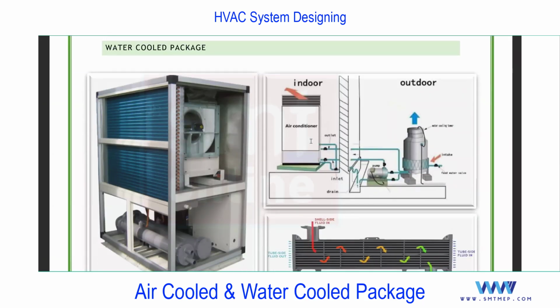Okay, so we'll just discuss the difference. The rest of the thing is same. Okay, so you see in the water-cooled package, here we'll connect the supply duct, return duct. This side is same, and this unit is placed inside the building. The air-cooled package must be placed outside the building because the condenser is an air-cooled condenser. No?